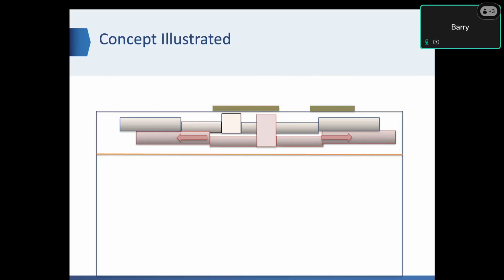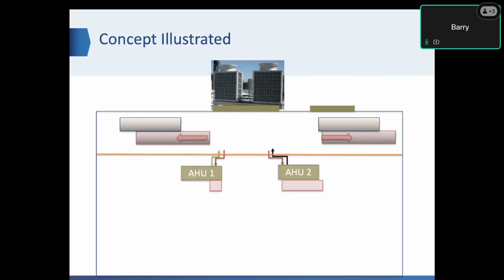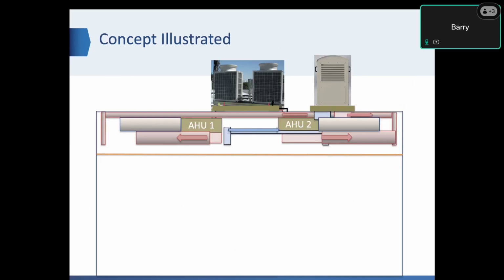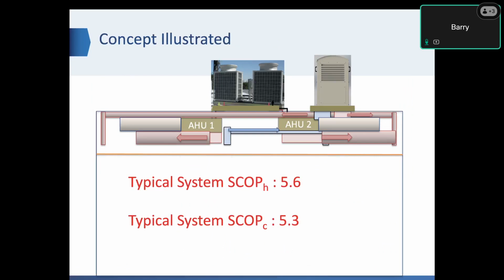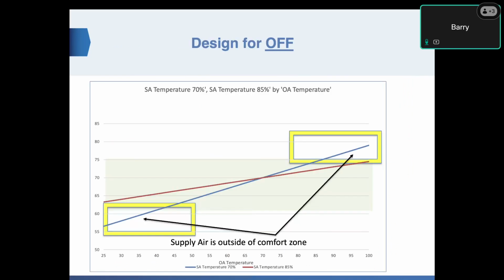So it looks like this: take rooftop units off, replace it with a heat pump system, air handlers, and a ventilation system. Again, seasonal COPs. There's heating and cooling, 5.6, 5.3, very high efficiency, very large savings on energy use. One other important thing is what we call design for off. These two lines, the blue line is 70% efficiency. The red line is 85% efficiency. That 15% difference has a very dramatic impact on the comfort of the air you're bringing in.